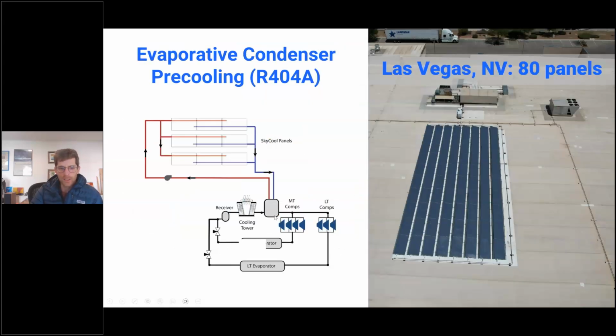In this particular system, there was an evaporative condenser. We have 80 panels. Again, it's connected with a refrigeration system. There are low and medium temperature groups or cases, and the goal for this project was to reduce water usage. Water tends to be relatively inexpensive, and so the ROI for this project is longer, but in places where you don't have access to water, or there are severe water constraints that you're expecting in the future, this can be a way to reduce water usage. And I can get into the specifics there.